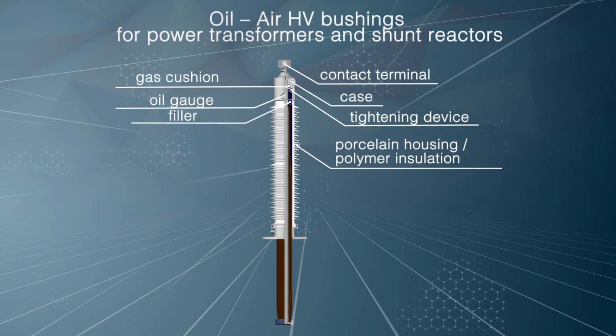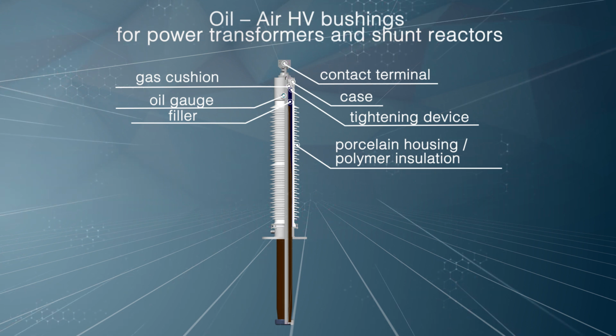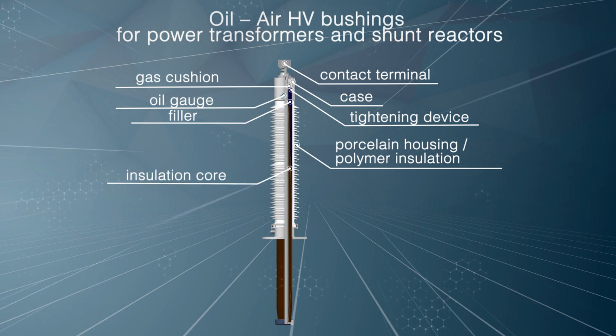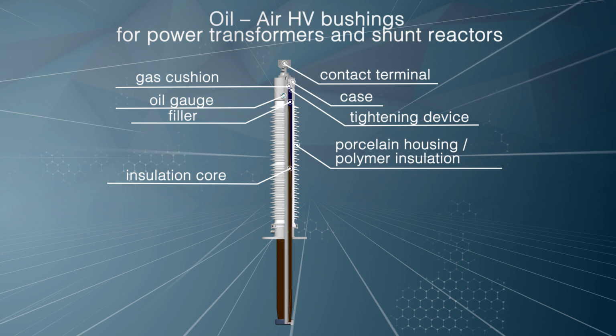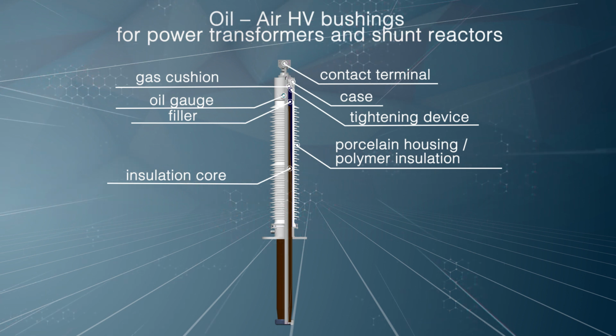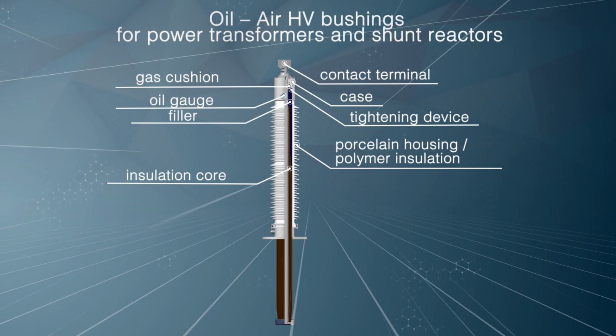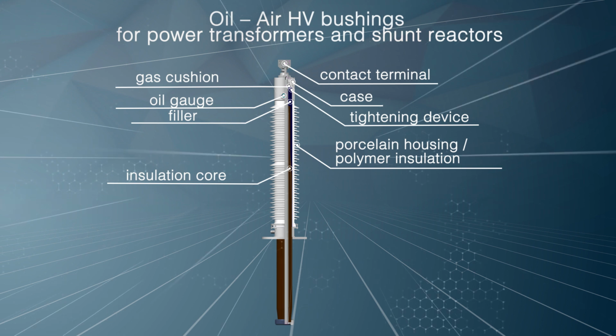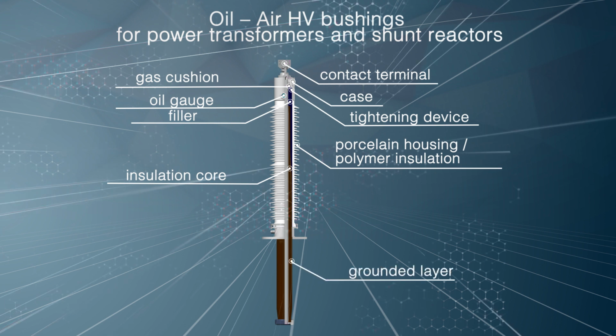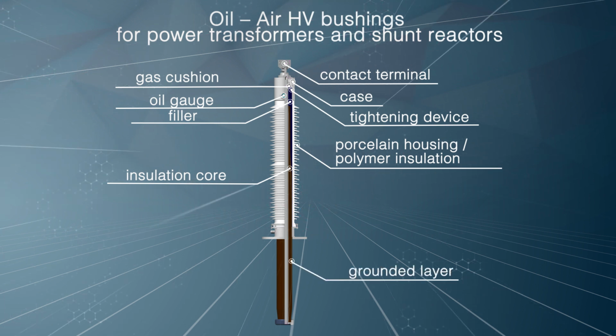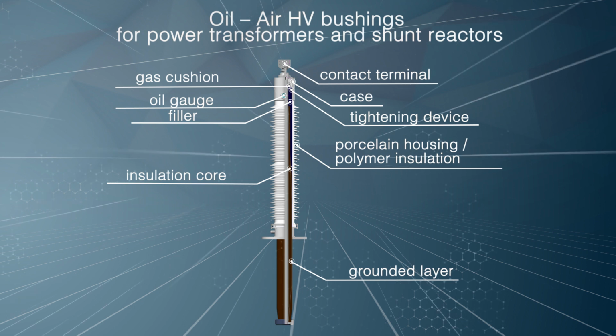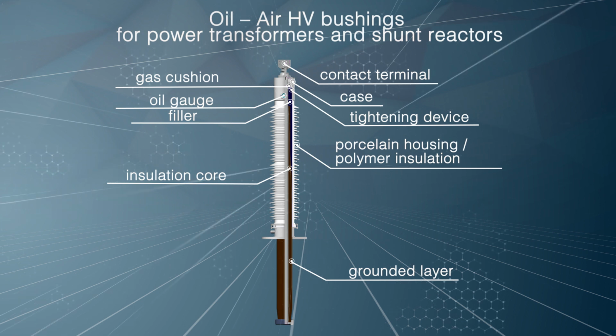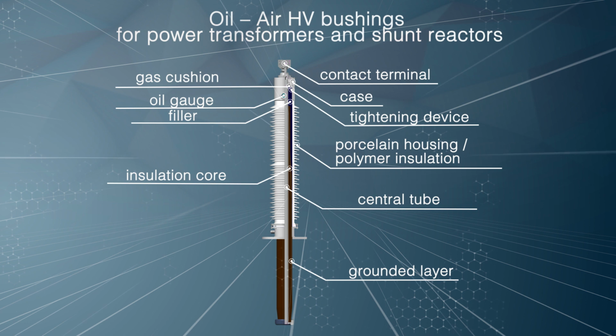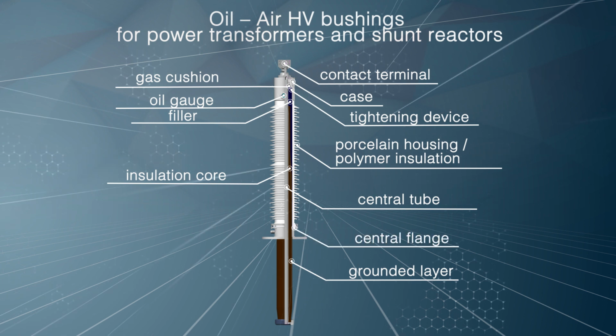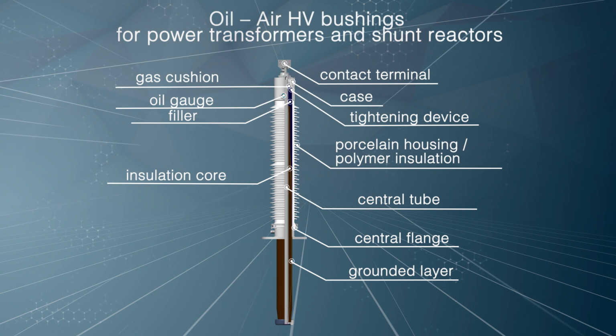Insulation core is an internal insulation of the bushing, equalizing electric field in radial and axial directions using condenser liners. The last layer of the insulation core is grounded in operation, hence it is called grounded. This layer stays in permanent electric contact with the measuring tap, which is used for taking measurements. So, the second name of the liner is measuring. The central tube is intended for winding internal insulation on it. The central flange is used for fastening together elements of the bushing. The test tap is placed thereon. The mounting flange is used for securing the bushing on the equipment.